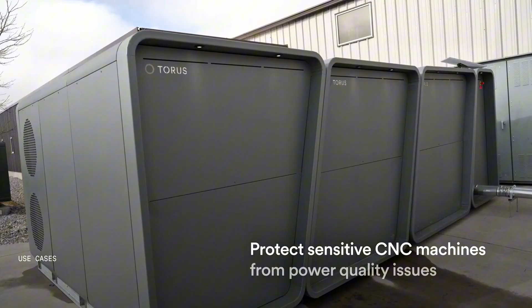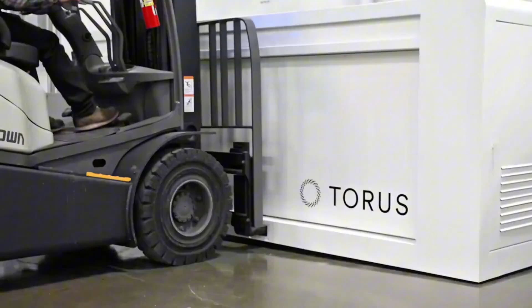So they built the Nova Spin, the flywheel system that reacts in under 250 milliseconds and delivers 20 times the power density of a chemical battery, absorbing the sharp spikes and power quality events that would otherwise grind lithium cells to dust. And they paired it with the Nova Pulse, a lithium iron phosphate battery system that handles the longer duration discharge, the hours of backup, the steady base load support that flywheels were never meant to provide.